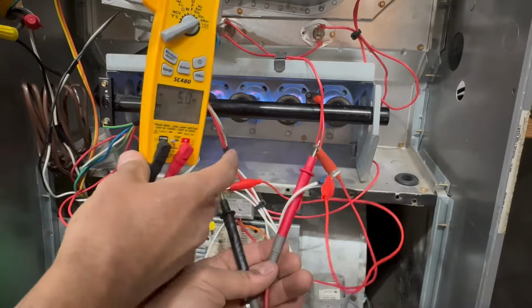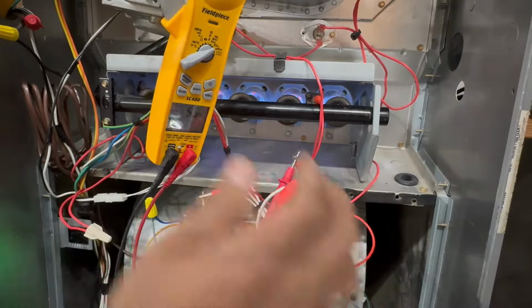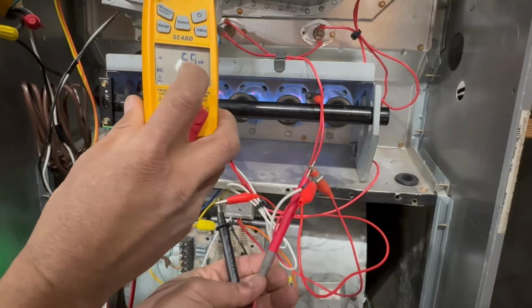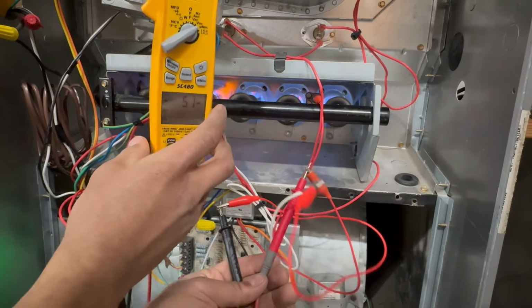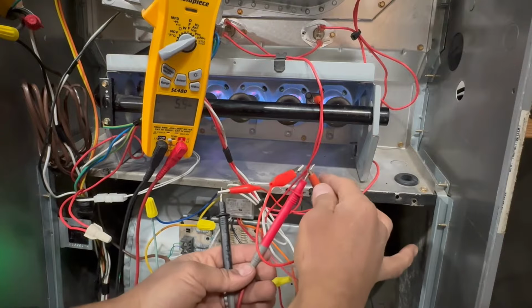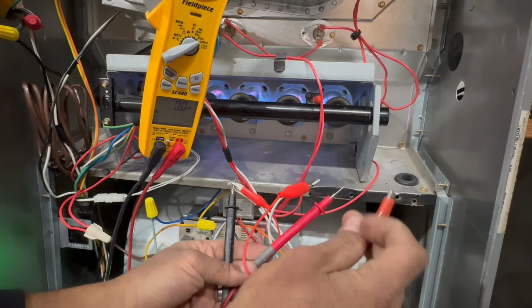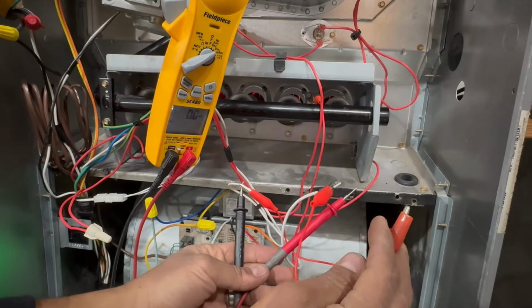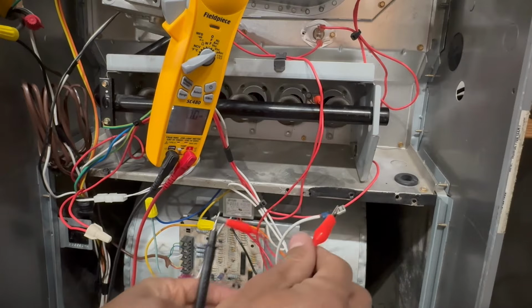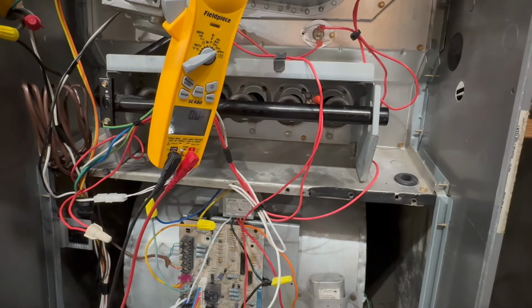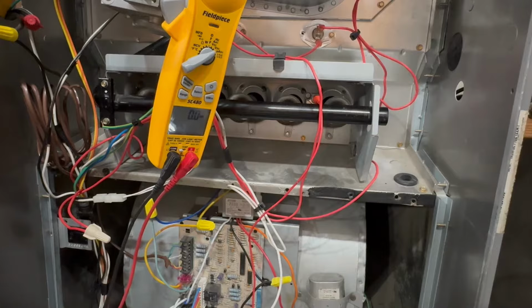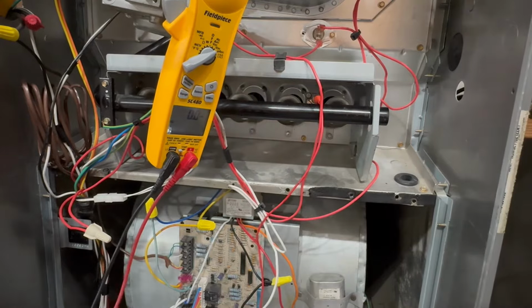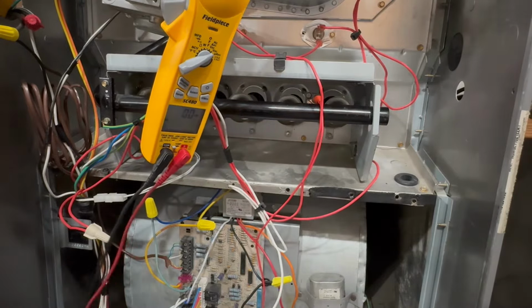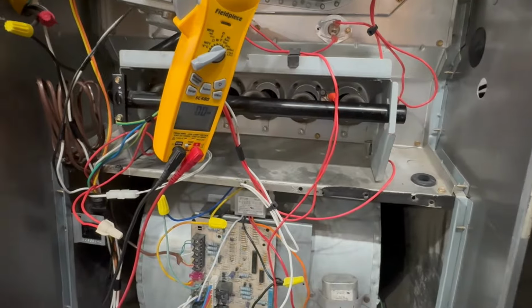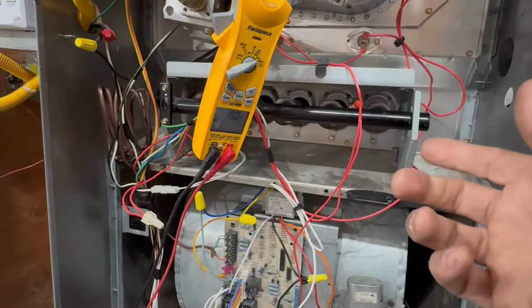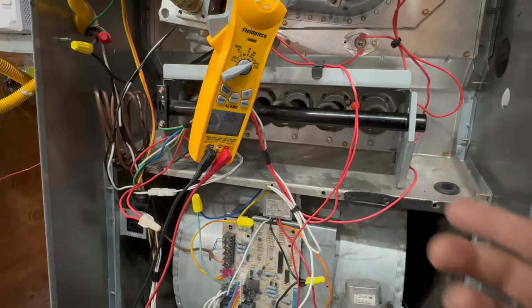But look at what I'm going to do right now. If I disconnect one wire, you see, so I just want to show you, we're getting a good flame sensor reading. If you disconnect one wire, I disconnected it, it's going to turn off because now it's no longer part of the circuit. So I just disconnected power, but I just wanted to show you guys when checking the flame sensor, that is what you're doing. You're making sure that the flame sensor is clean.